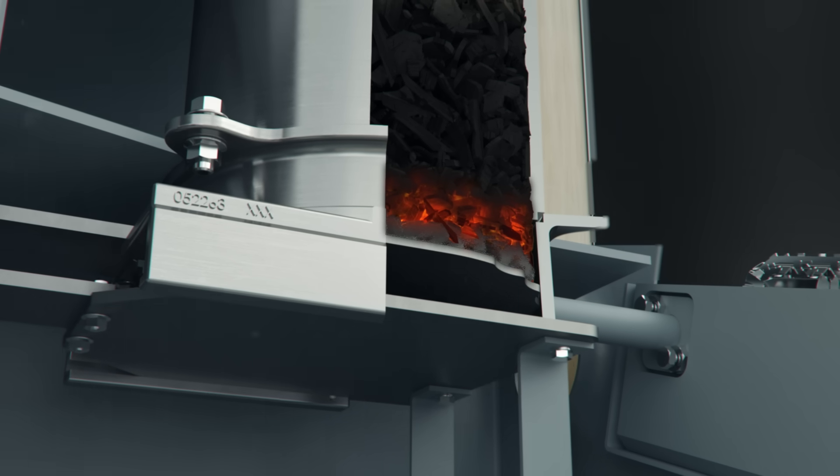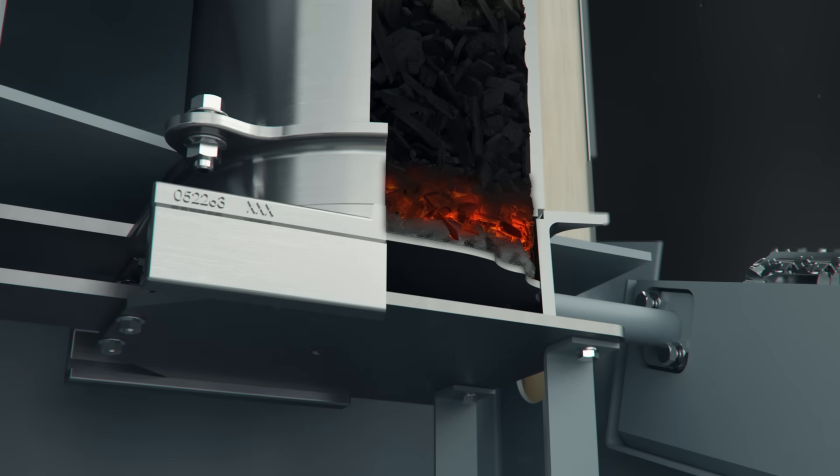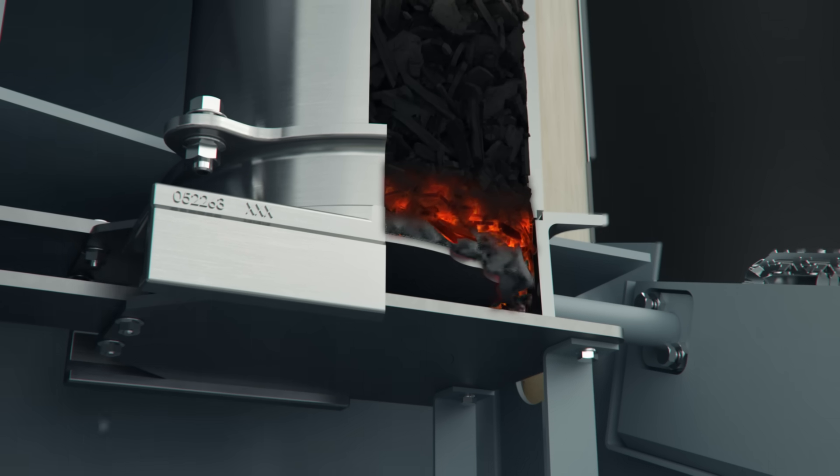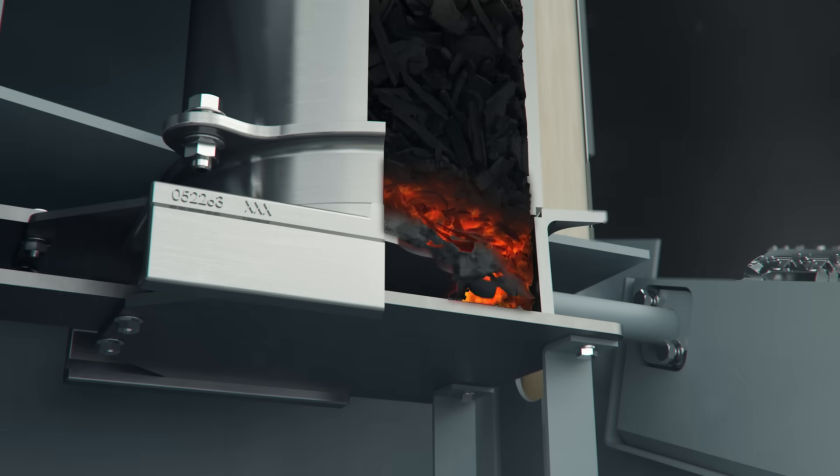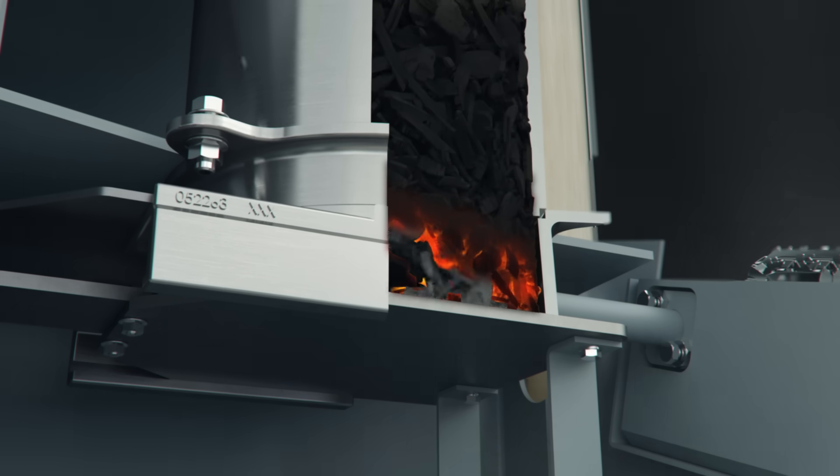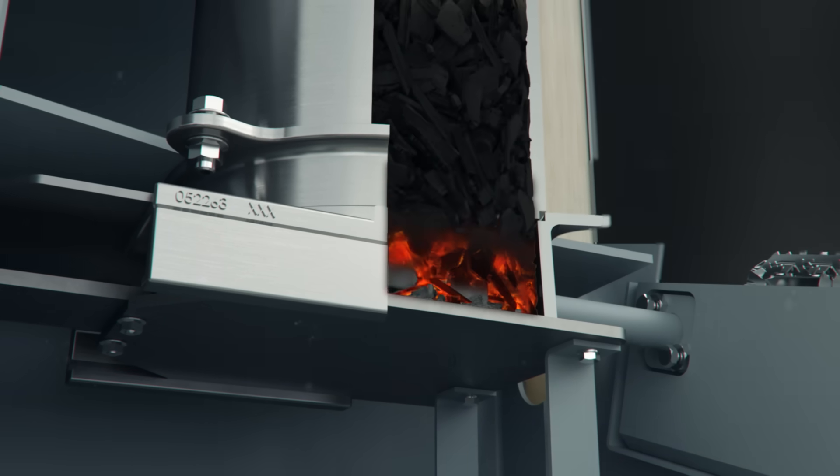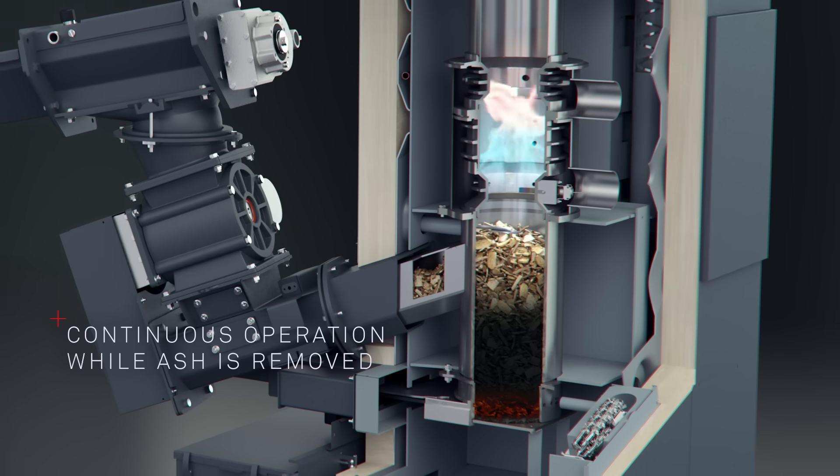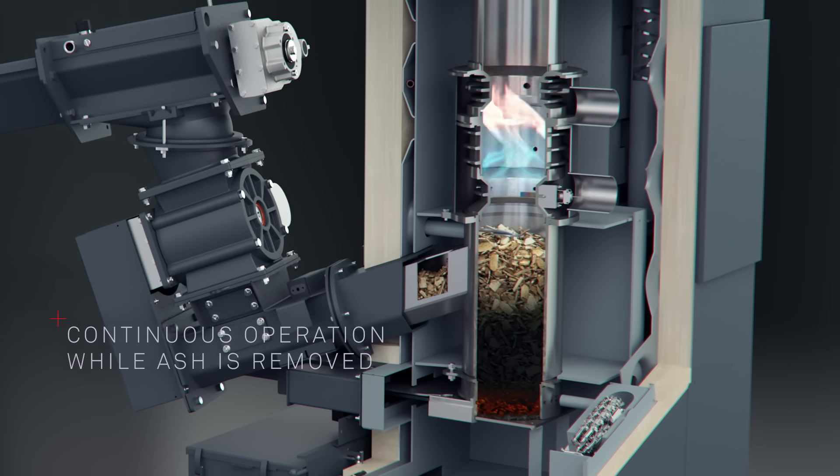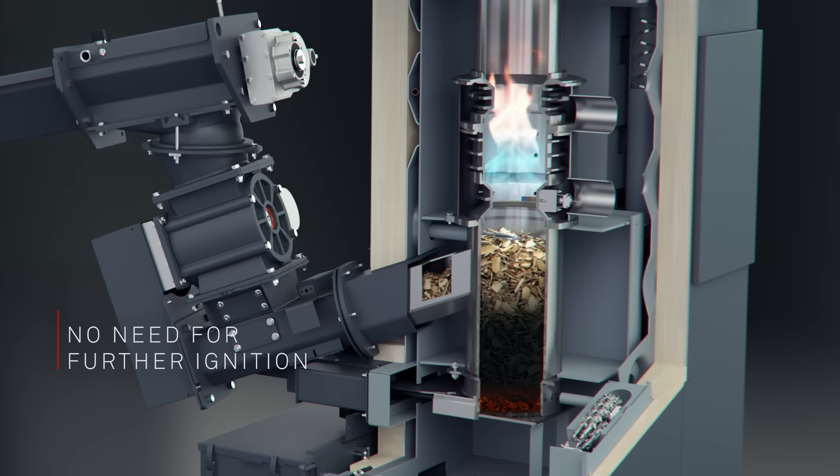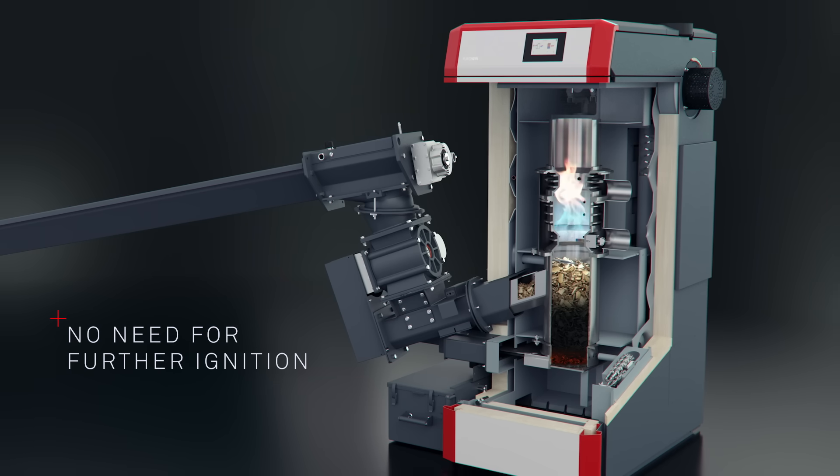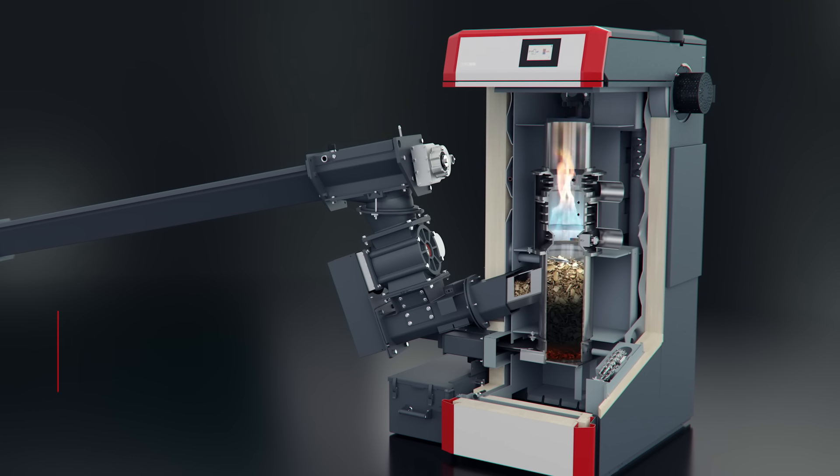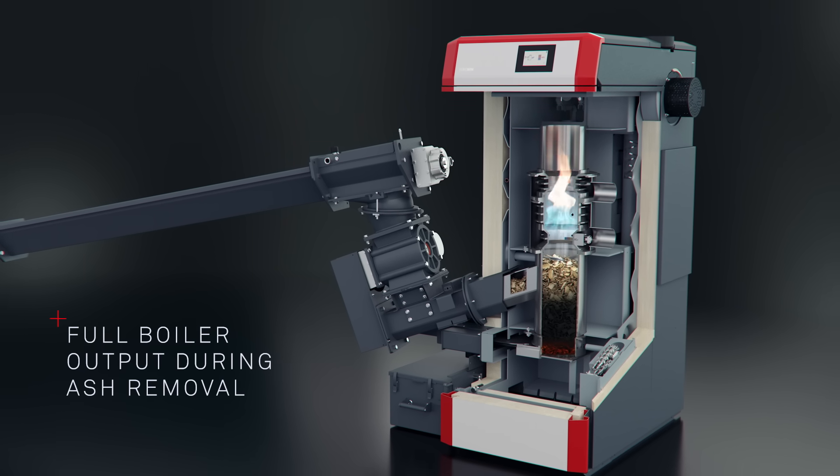The ash removal plate closes again and the ember bed slide above it opens, causing the ember bed and wood chip to slide through. Through this process, our development engineers ensure that the PuroWin can be operated continuously. There is no need for further ignition and ignition energy is thereby cut. This procedure also means that the boiler output is fully maintained during ash removal.